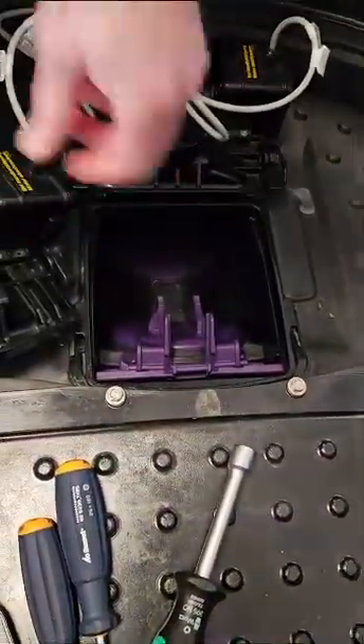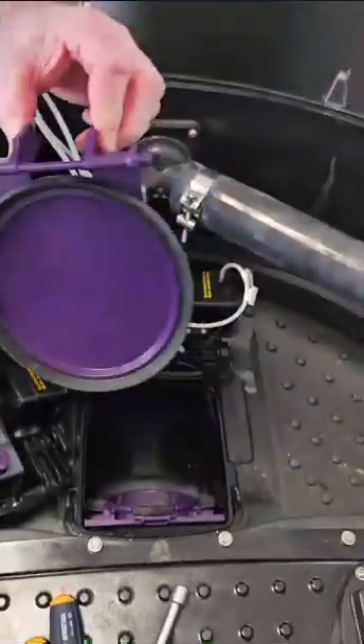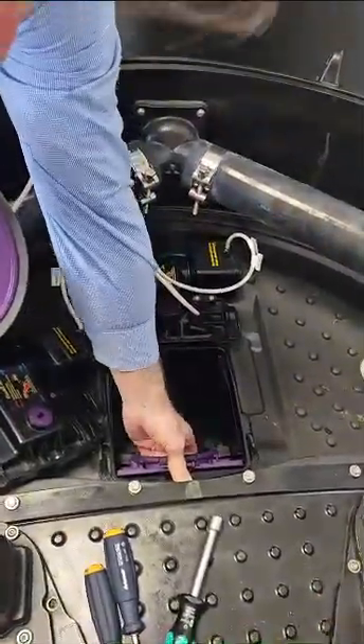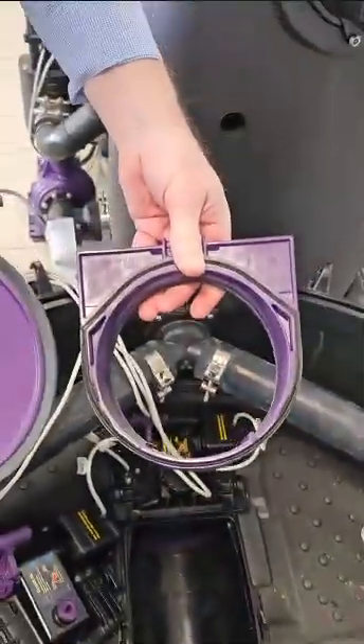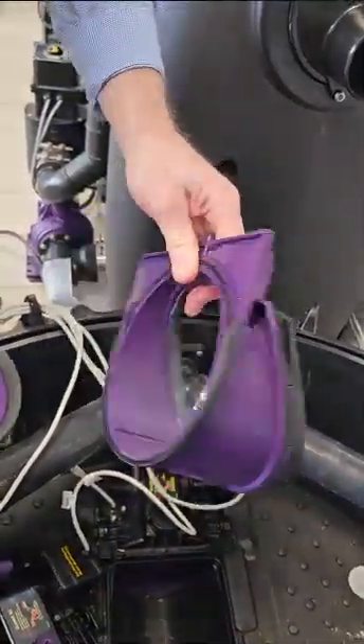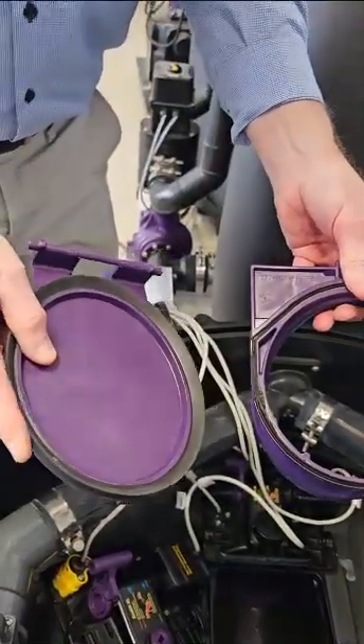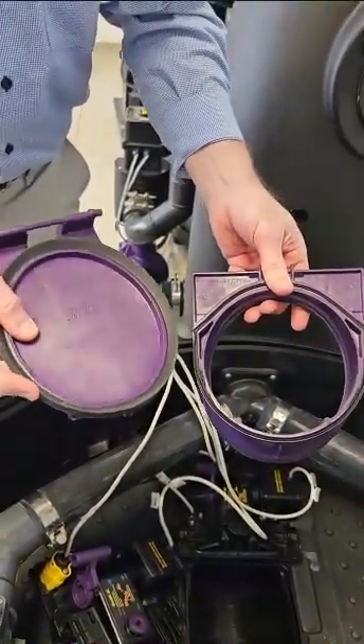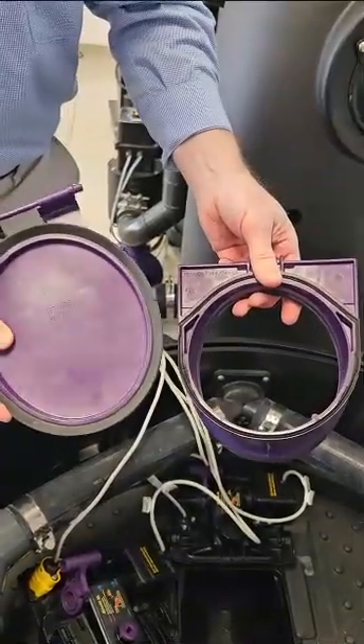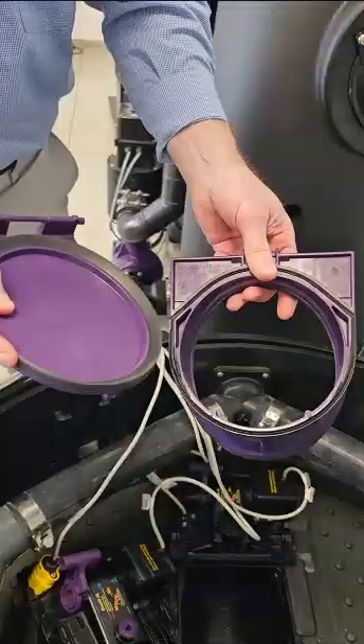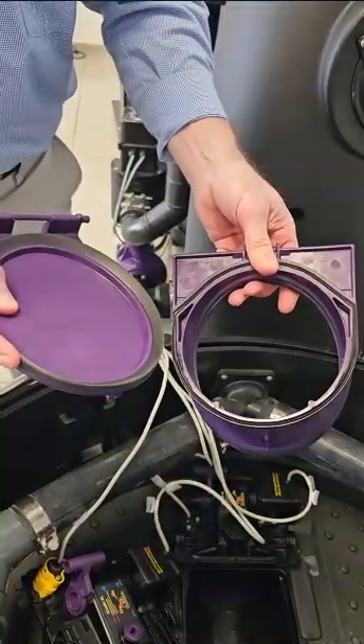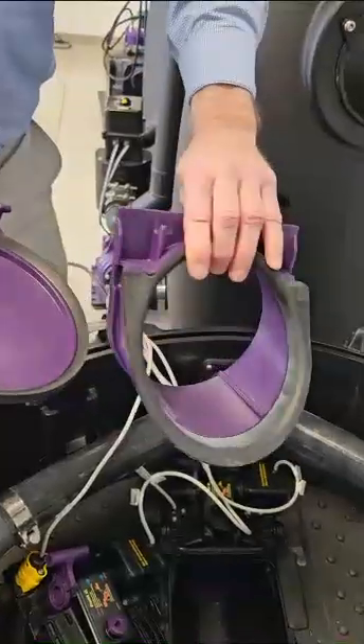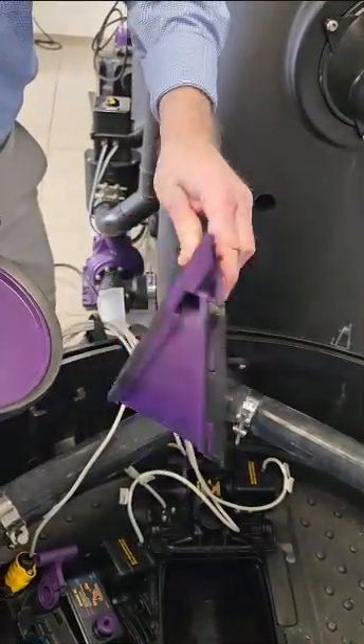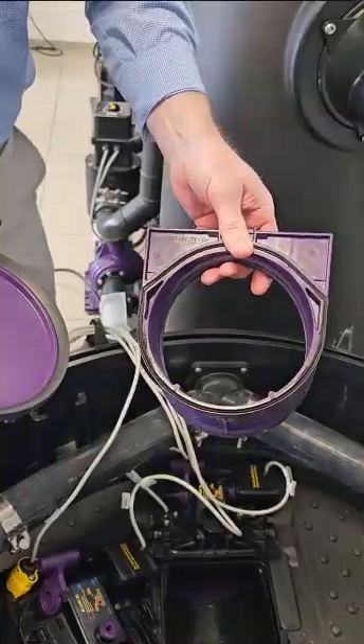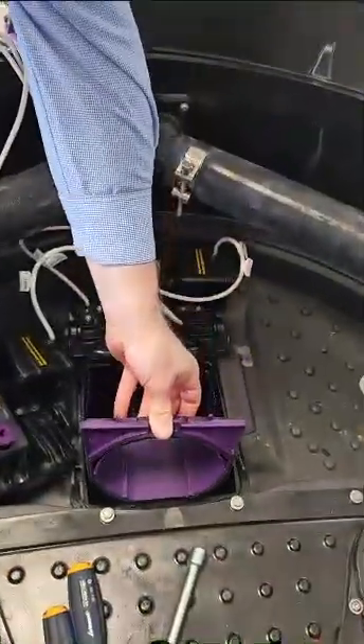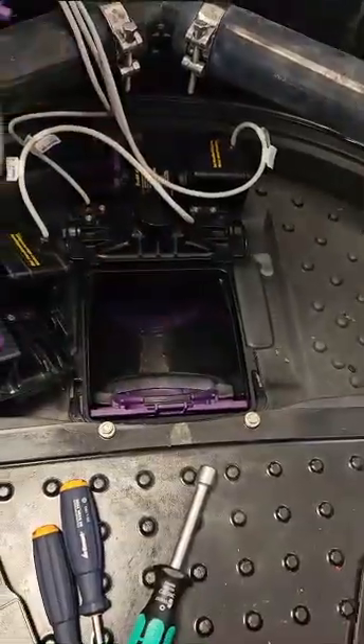There's 2 automated flaps here, both with housings. These housings need to be removed. There's 2 finger clips that move into the vertical position and also automatically prop the cover out. This entire housing gets removed. You see here one of the 3 optical probes. If you clearly see water in the optical probe or moisture condensation in it, that could be a sign that the optical probe is damaged. But this is a dry optical probe. Everything is in good condition here.